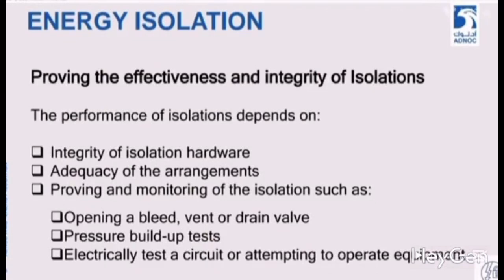Adequacy of the arrangements. You should have measurements before putting the blind. Which gasket to use, which bolts to use, how much torque to keep, what will be its quantity and strength. All things should be arranged beforehand so that when you do isolation, you can perform a good action according to proper arrangement. It will be based on how authentic your isolation is, how effective it is.